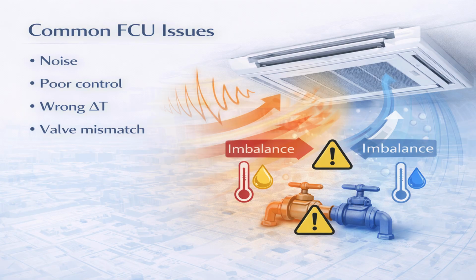And very often, the first complaint is not temperature, it's noise. A rattling, whistling, or constant fan sound is usually noticed long before anyone talks about cooling performance. By the time thermal discomfort is reported, the dissatisfaction has already set in. This is why FCU selection must consider acoustics, control stability, and realistic operating conditions, not just airflow and nominal capacities. Getting these details right makes the difference between a quiet, comfortable space and a system that generates complaints from day one.